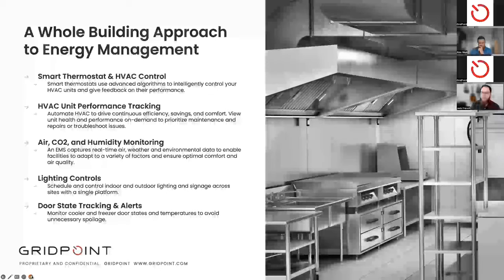Another additional piece of an energy management system that can be really helpful is indoor air quality monitoring, which is where we come into CO2 concentration and humidity monitoring. These could inform decisions. If you have ongoing CO2 and humidity issues, you may want to consider adding a makeup air unit to your system, or opt into some of the algorithms offered, or add a unit with hot gas reheat to mitigate humidity. By tracking all of these metrics, it can allow you to make informed decisions on where you should spend your capital, where you have potential issues, and what you can do to solve those issues. Can you solve them with the existing infrastructure, or do you need to consider a retrofit?